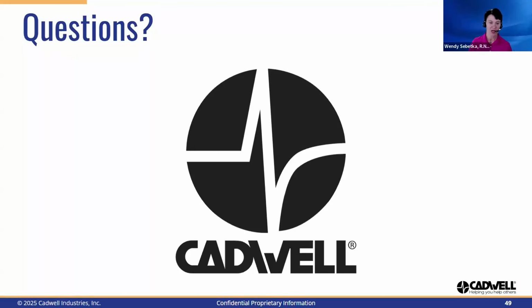So next question, can I run the machine without earth grounding? It is not recommended. You can run the machine, but you're probably going to experience a lot more of that outside interference, that 60 Hertz noise and things like that. Earth grounding is definitely going to be a big factor in cleaning up your responses.